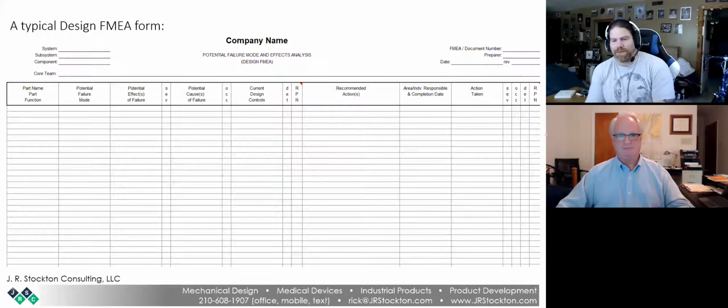They might even be made by different teams. They might look different, but don't try to combine them because you think you're saving yourself paperwork, because they have two totally different purposes. And when we're submitting a 510K, we don't submit risk management for the most part, except for software. So you might not need anything for the 510K.